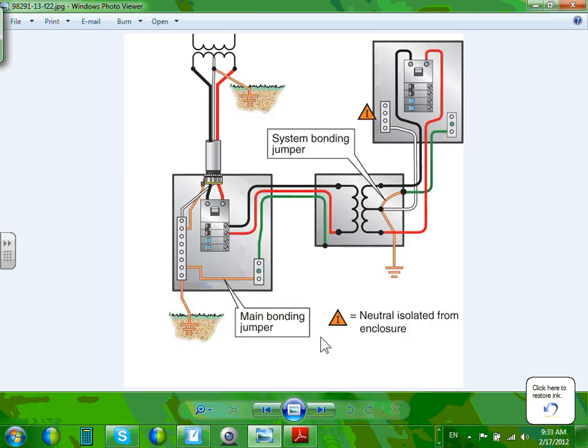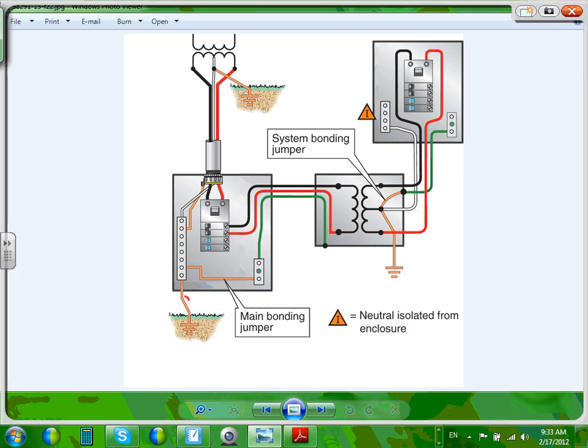Equipment bonding jumper, every time you have to bond across equipment if they are not continuous. I want you to look at this one, guys, and for the time being, please identify the following. This is my service. This is called main bonding jumper. Can you guys see that? That's the only thing I want at this time. This is grounding electrode conductor, main bonding jumper. And this one also grounding electrode conductor.